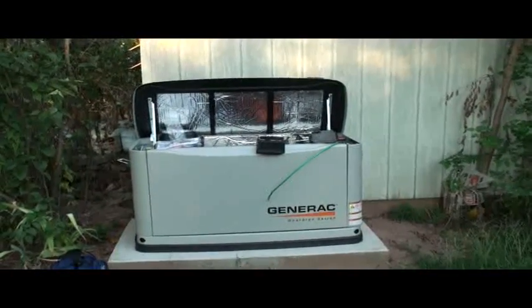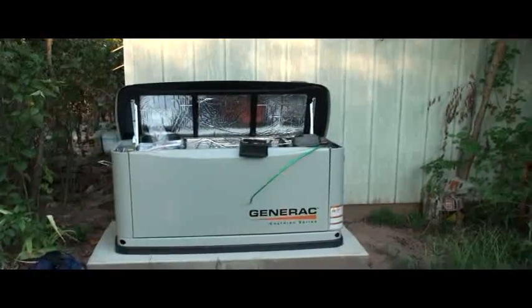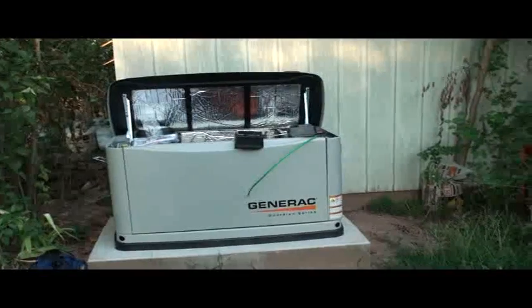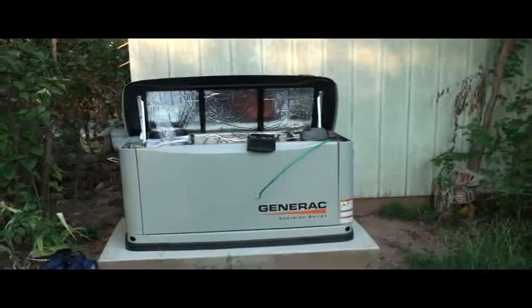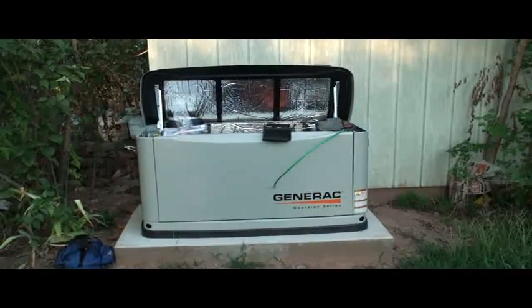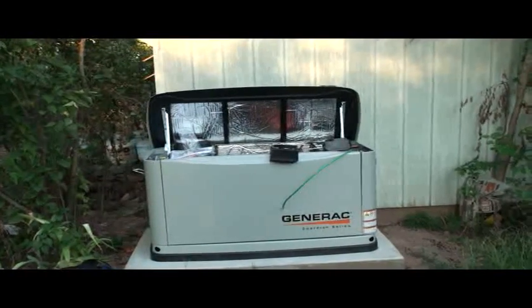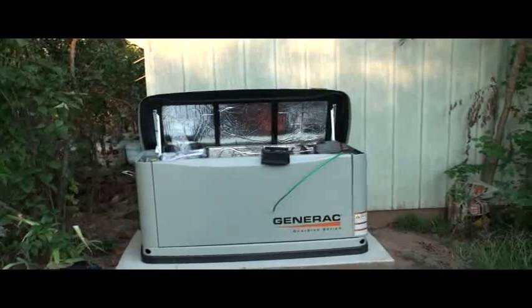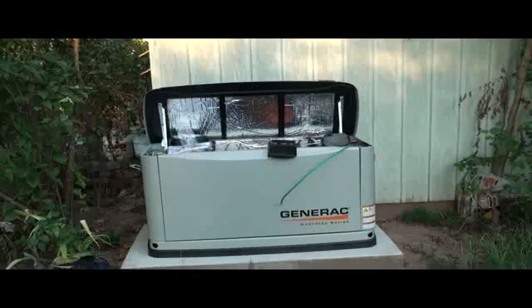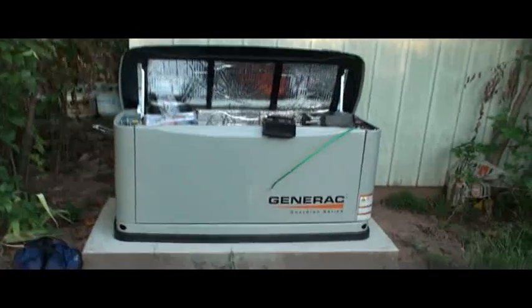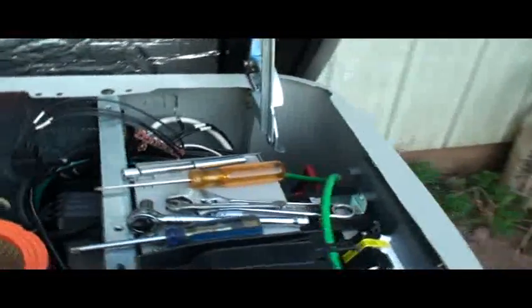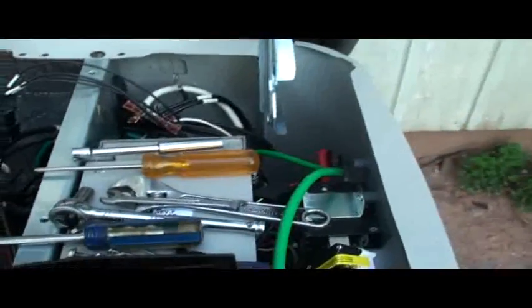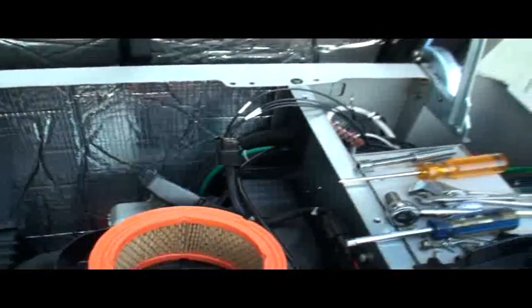So this is basically just documenting what I did, and it might be something that they want to look at. Maybe they need to redesign part of it more, or this may be a better option for other people who want to run the larger cable and don't want to deal with the problem. When I was hooking up the ground and the neutral, which are the two that I have the problem with, they won't fit into the ground bar.